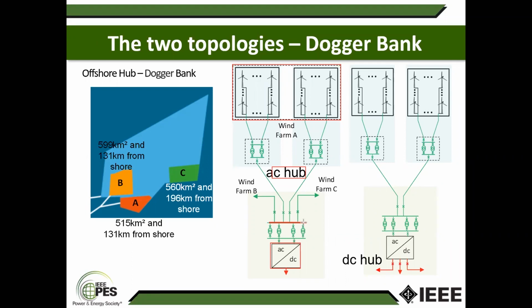If you look at the one on the right, you can see that wind farm A is first connected to the AC-DC converter, and at that point the wind farm B and C are connected. So it's a DC hub, basically you have a DC bus bar. Now the AC hub is favored against the DC hub. Main reason is there are still no commercially available DC circuit breakers, even though there are a few competitors working on it. They are still not in the mainstream.